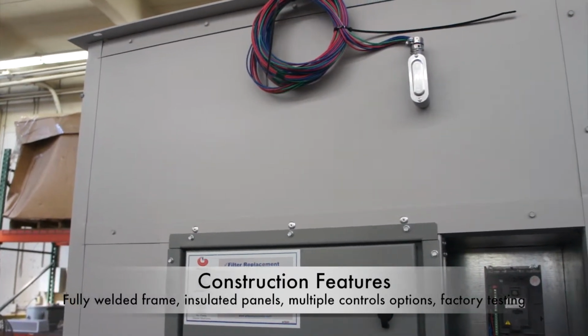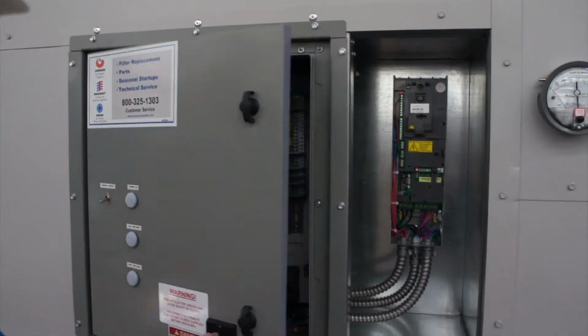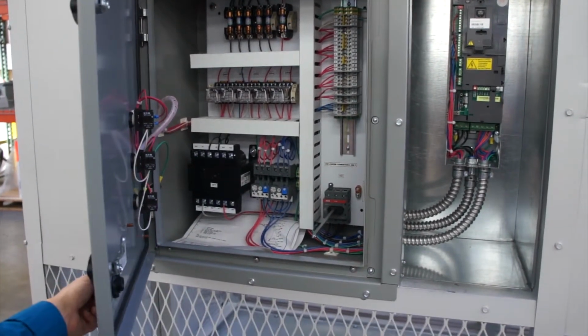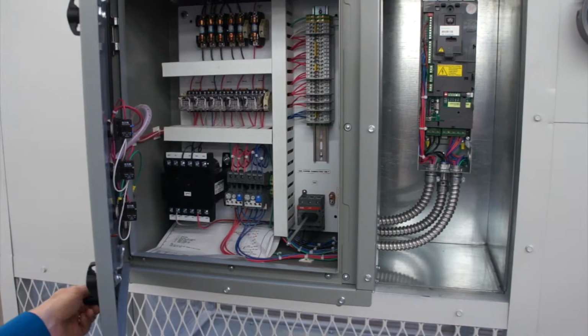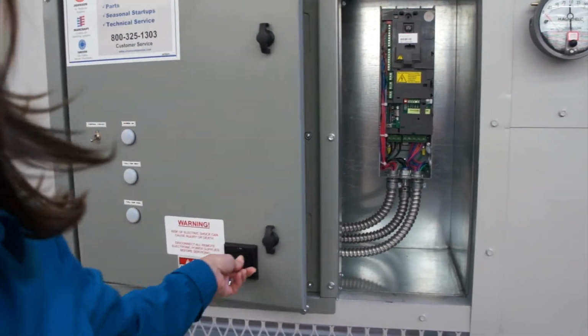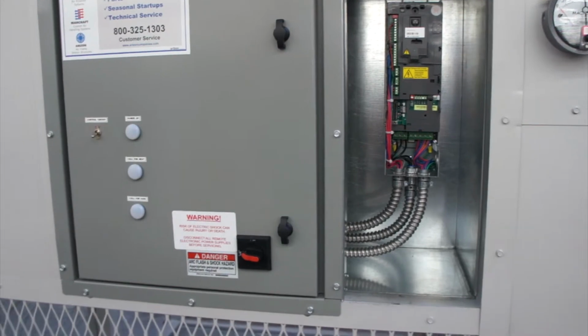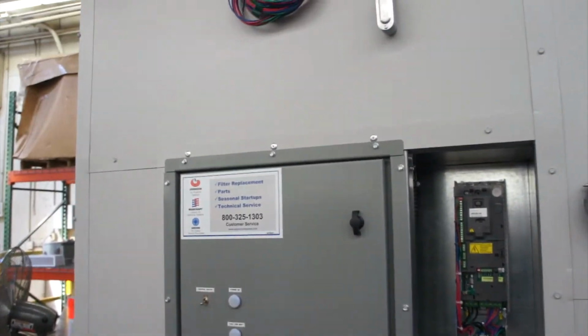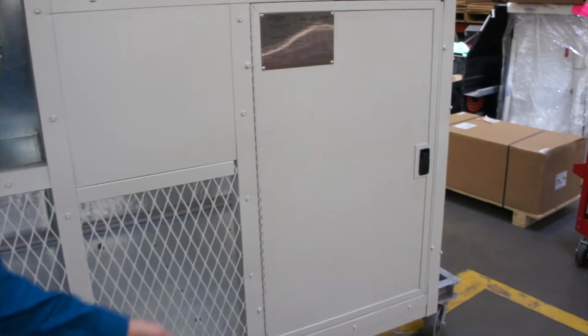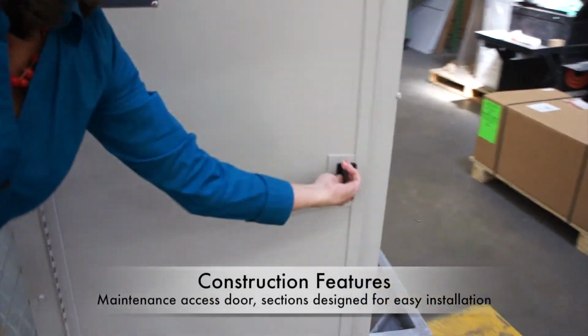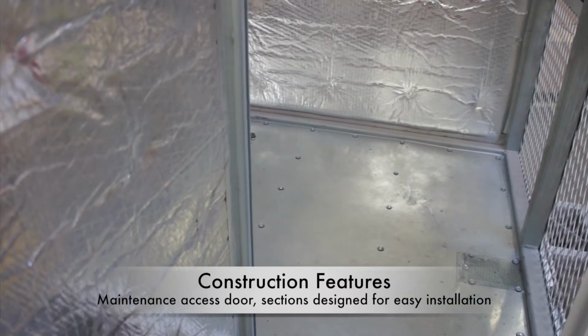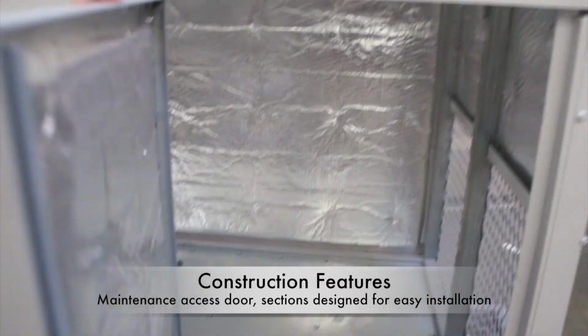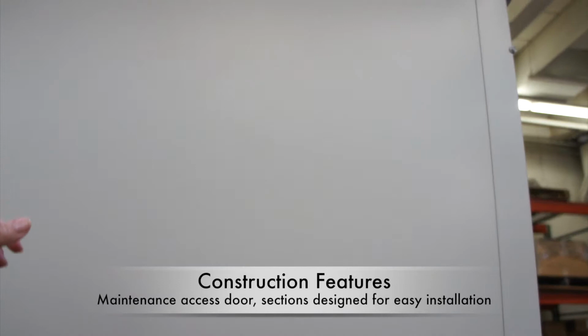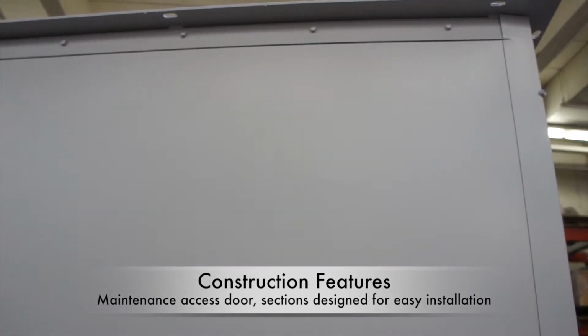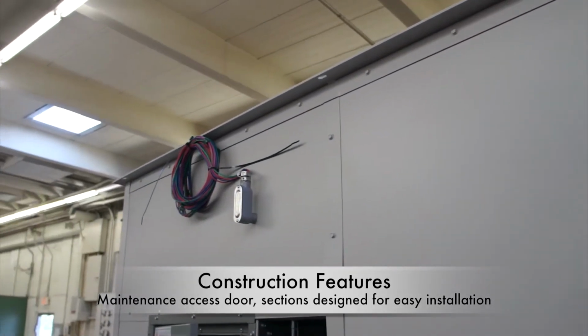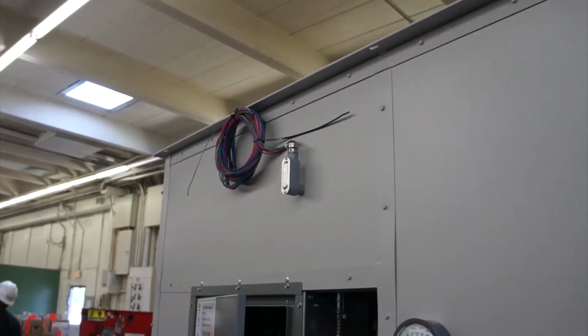We test each one of our units. We do all the electrical controls, and we put them through a fully assembled test depending upon whether it's just electromechanical controls or DDC, BACnet, Modbus, or Ethernet. Every single section that's located on the floor has a large access section for ease of serviceability and maintenance. Additionally, these units have flanges for easy installation. Each section is stacked one on top of the other, and the flanges are punched to match, so it's very easy to stack.